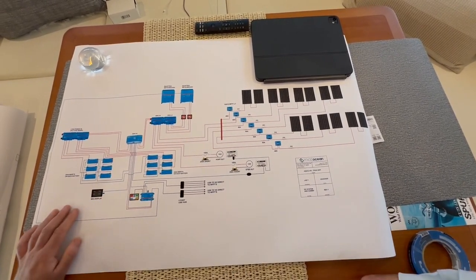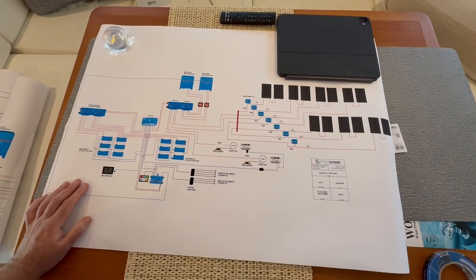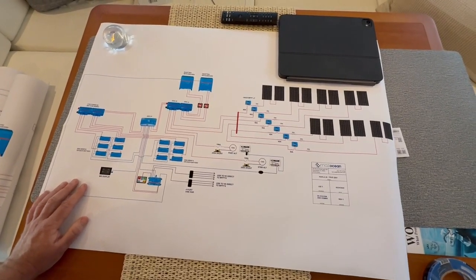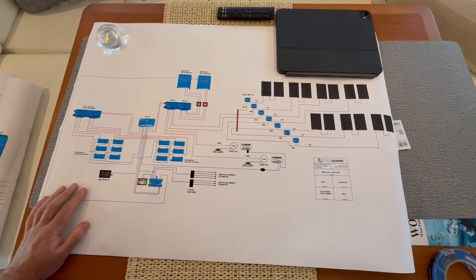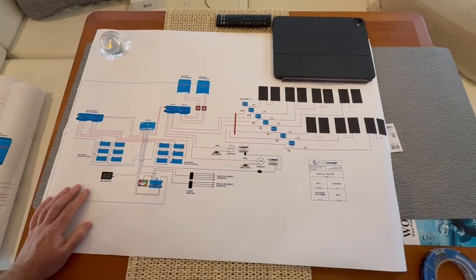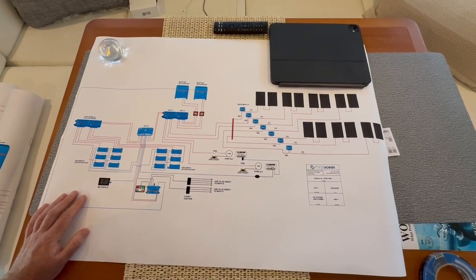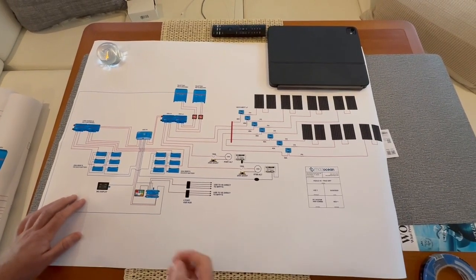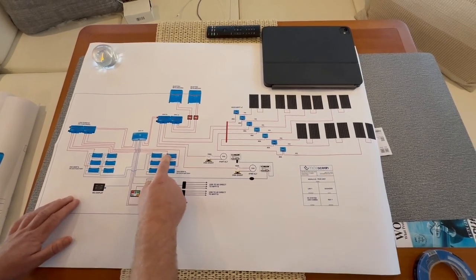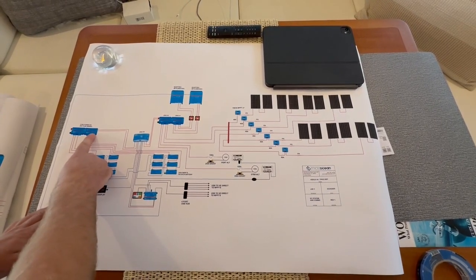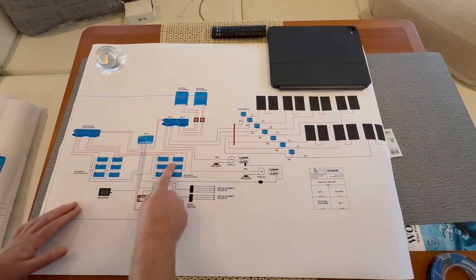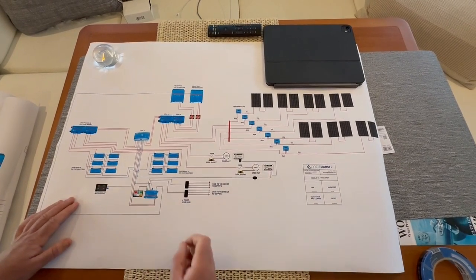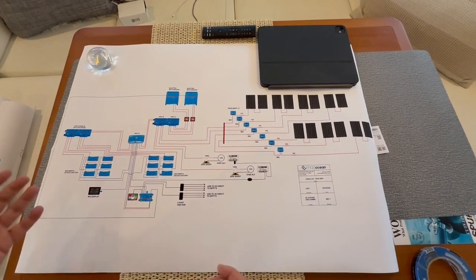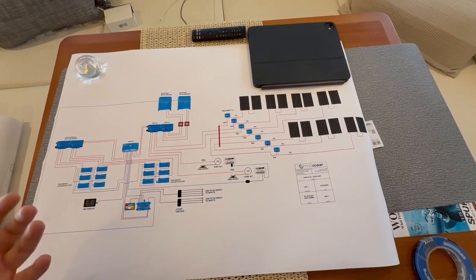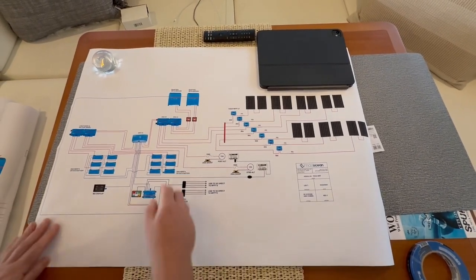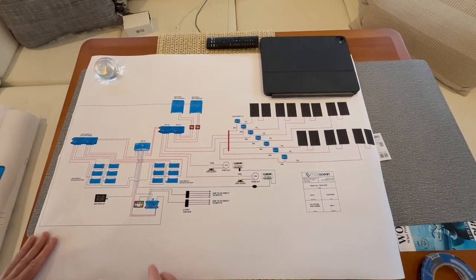One of the things with lithium is cell balancing. Inside each battery there are a number of cells, and those cells need to be balanced with each other—lithium doesn't like to get unbalanced. One way to achieve that is making sure that from each battery to the distribution point, these wires are identical in length. Because if the wires were different lengths, you'd get different resistance in the wires, which could affect the cell voltages inside the batteries and cause problems.